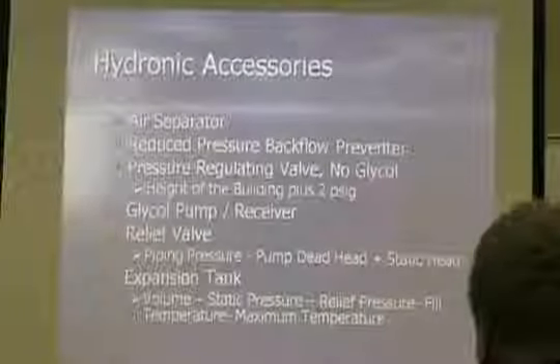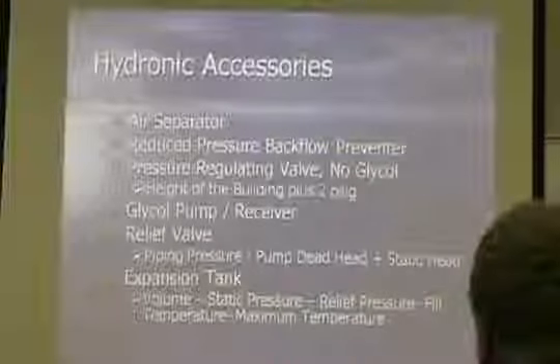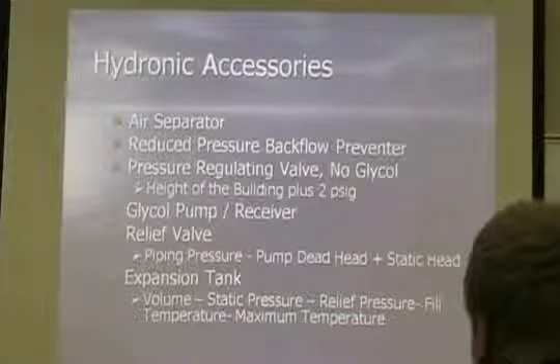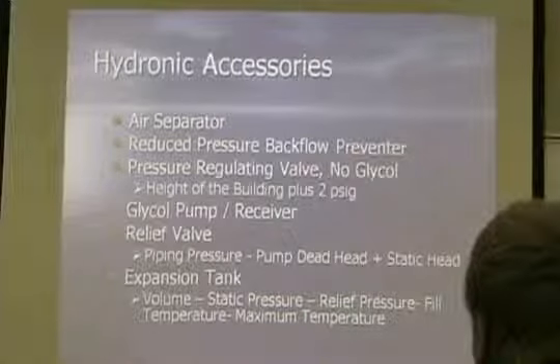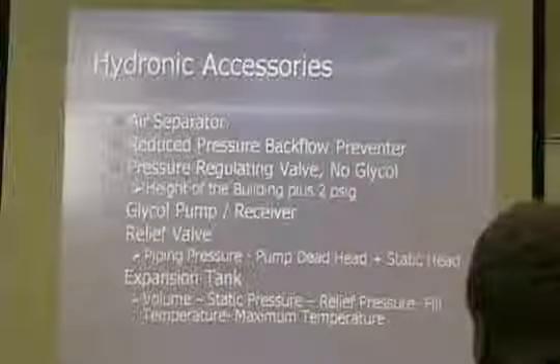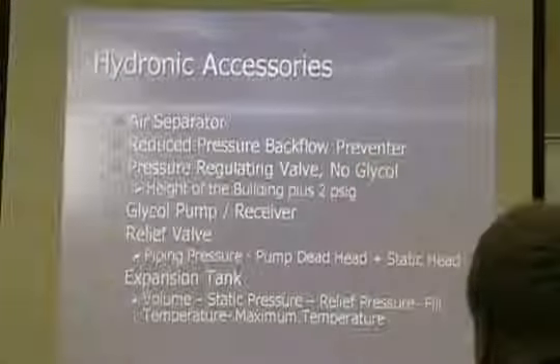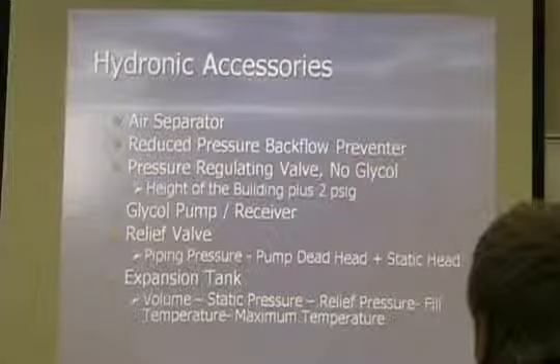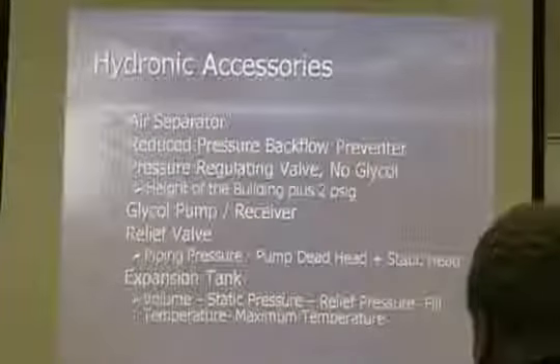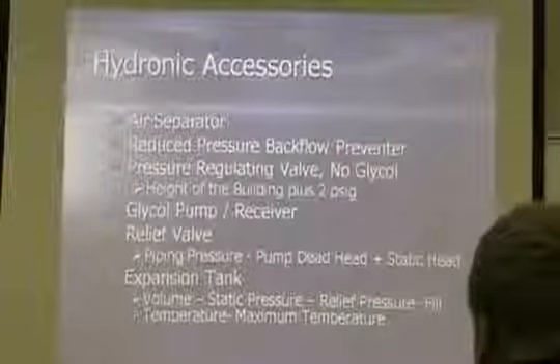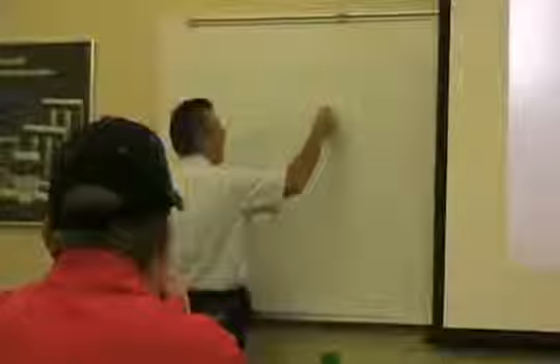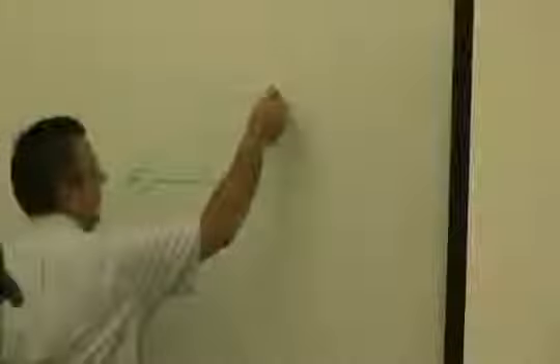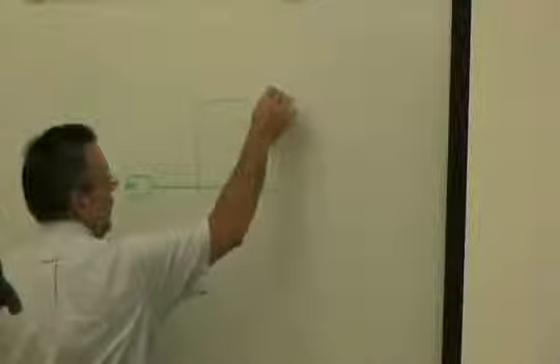Regulating water systems, we talked about how you size that bypass valve. If you do have glycol in your system, and lots of water source heat pump systems, especially geothermal systems, have glycol, you've got your circulating water pump, and you've got your relief valve. And we talked about that makeup valve, the size for the height of the building.